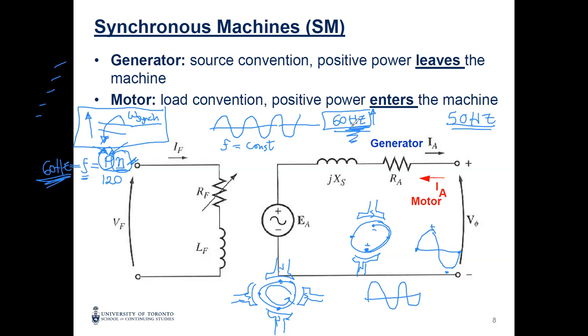I told you something here that is not 100% accurate, and we will discuss it today: that the frequency is exactly 60 hertz and always constant at 60 hertz. In reality, the system is dynamic, loads are coming, you may have a generator outage or something, so sometimes we have slight changes from the 60 hertz, and it depends on the events you have. But in normal cases, you should have 60, almost or close to a constant value.